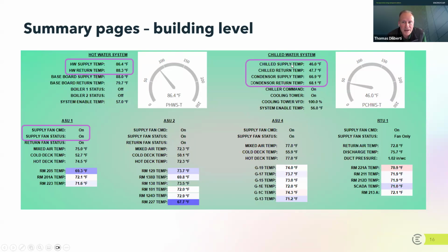So chill water supply, cold water going out to the building, is at 46 and it's returning at 48. So it's warming up, picking up a little bit of heat as it goes around. And this right here, condenser supply and return, suggests that you have a cooling tower. As you learn your systems and understand what these set points all mean, there are little indicators here to understand what you've got out in the field.